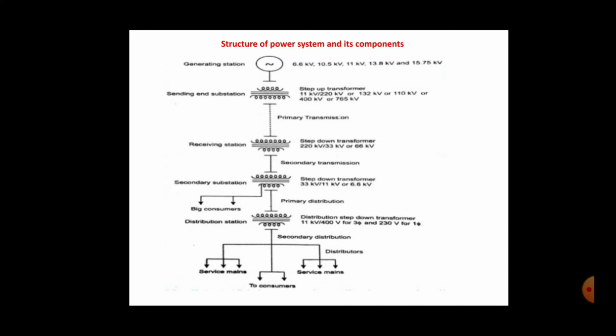Next, at the power sending end station, the generated voltage is stepped up to the primary transmission level, in the range of 66 kV to 765 kV, using step up transformers. So the electrical power can efficiently make its long journey in primary transmission lines. These high voltage transmission lines terminate at a substation called the receiving end substation. At the receiving end substations, the voltage is stepped down to 220 kV or 66 kV or 33 kV, and the electrical power is transmitted in the secondary transmission system.